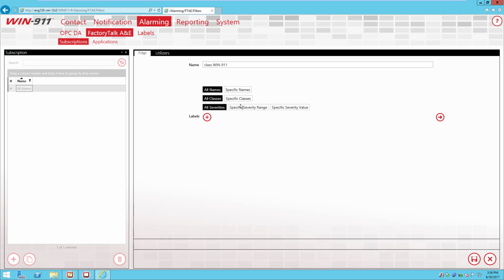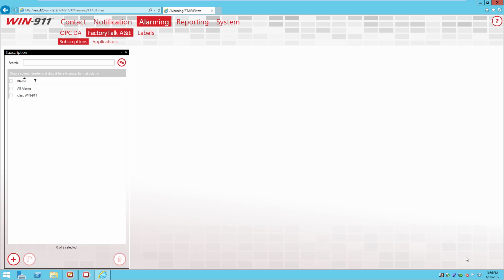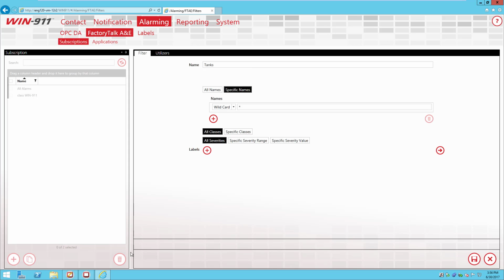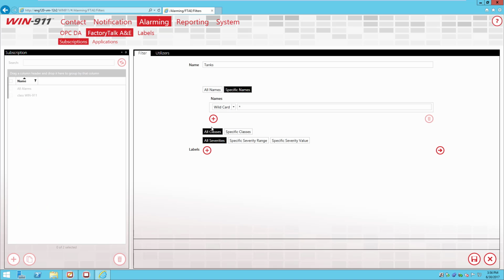So we'll call this subscription class Win911, and then our filter criteria is going to be a specific class. And we're going to say any class that contains Win911. The next kind of subscription I'll create is one for tanks. So I'll call this one tanks, and here I'm interested in filtering on a specific name. So if I want just these 2 alarms and not this gate valve, both of them have tank in their name. I can exploit that here.